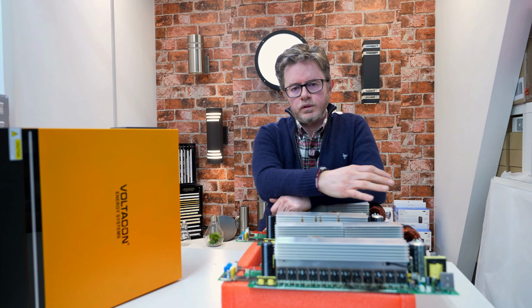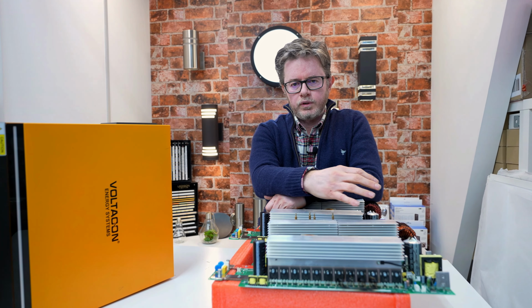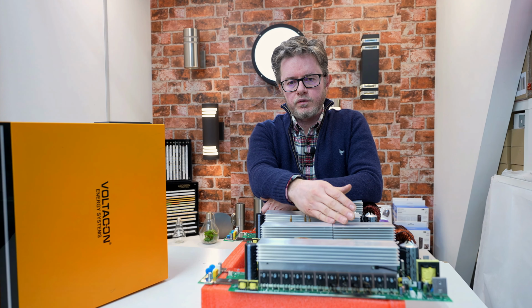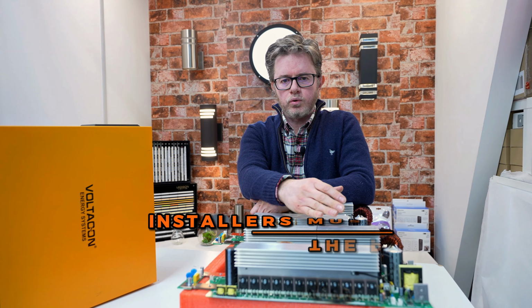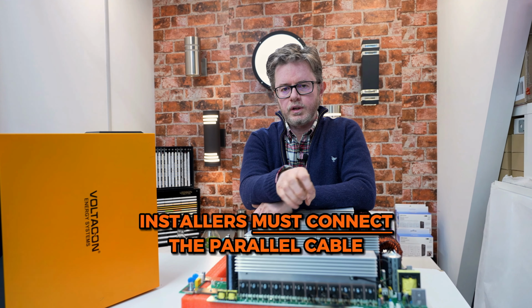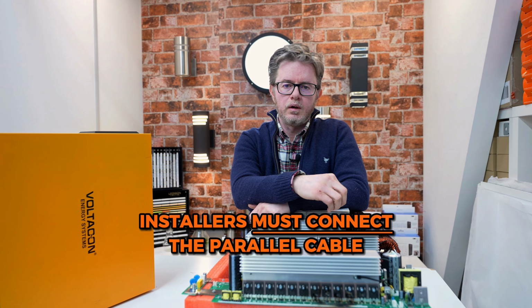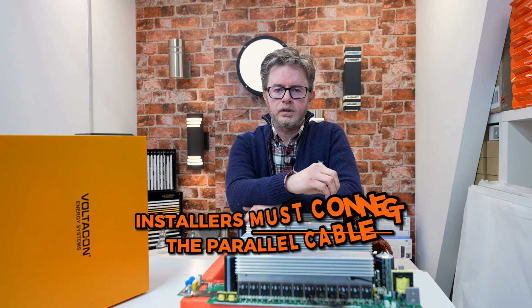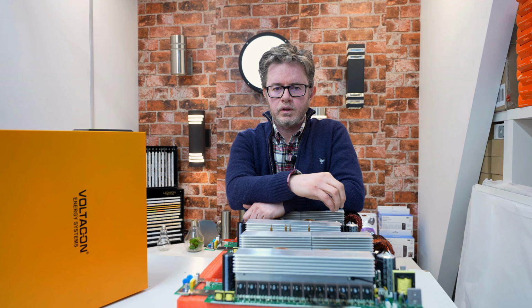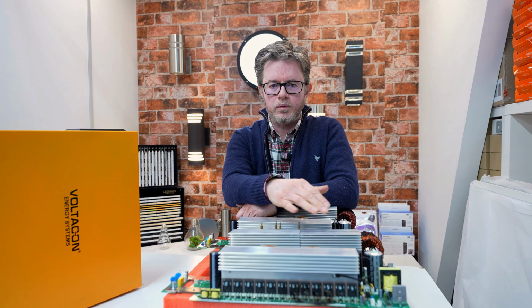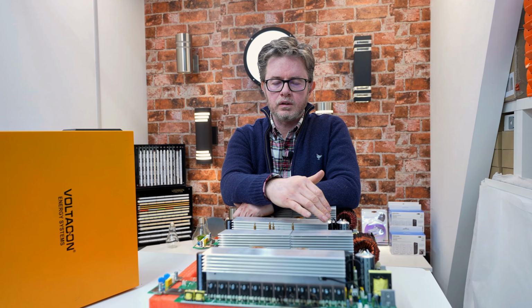We have issues when the installers put the parallel kit wrongly, and we have issues when the installers don't connect the parallel cables at all. They put the AC output together, but they forget to connect the parallel cables, and this is a terrible mistake, because it's going to blow up the inverters instantly.